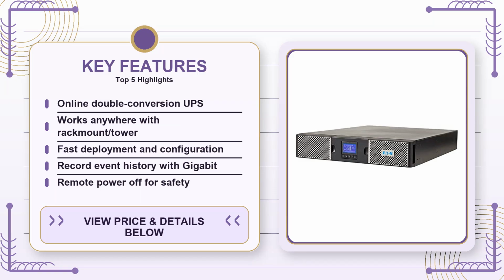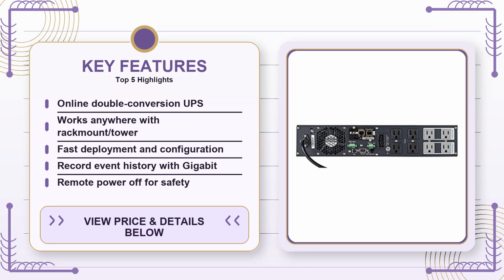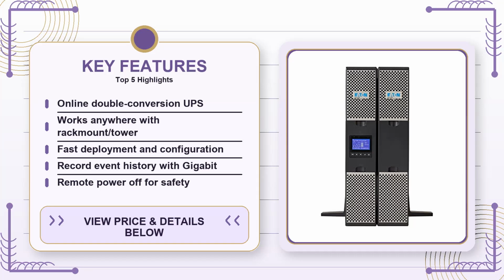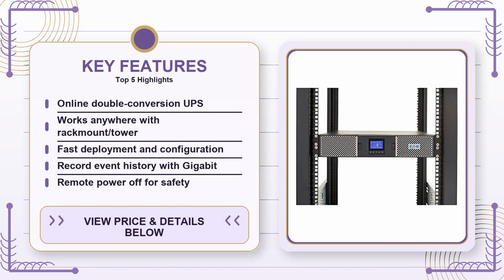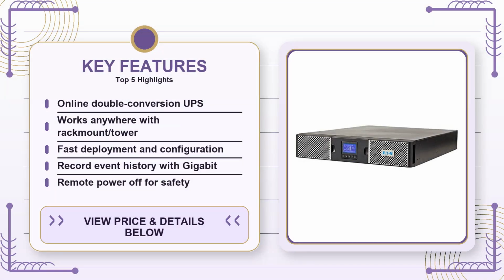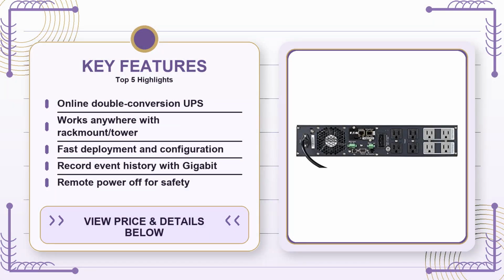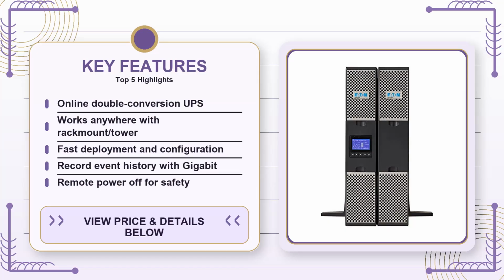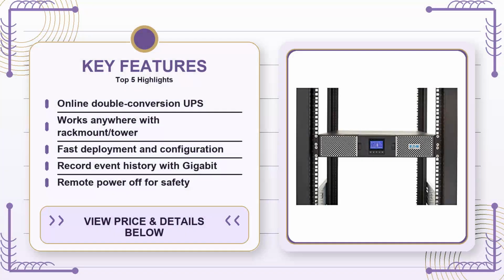Who should actually consider this unit? If you have a rack of 2U or 4U servers, a few network switches, and perhaps a NAS that you can't afford to lose, the 1500VA rating, which translates to about 1350W continuous output, gives you enough headroom to keep everything online for roughly 5 to 10 minutes during a typical power outage. That window is usually enough to either ride through a short brownout or to gracefully shut down services through the UPS's built-in communication ports. The 9PX also offers a built-in Gigabit network card, so you can monitor the unit remotely, pull event logs, and even set up automated alerts if the load spikes suddenly.